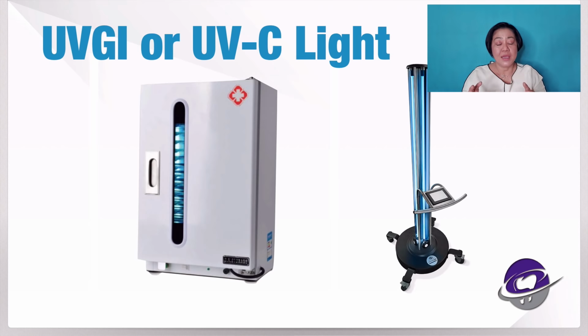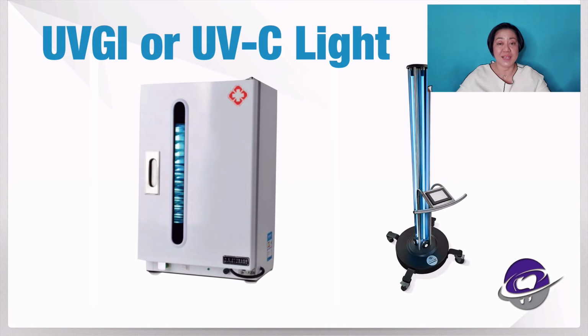However, as I've said, there is still a discussion whether it can be considered as sterilization or just simply disinfection. But for me, I feel that if you have a clinic that serves a lot of patients, then I think the best way to do is clean all the surfaces first and then run this UVGI or UVC. Now, when you buy this, make sure that you understand how big your room is, because again, just like the autoclave, the light has to have direct contact to the surface for it to really work. So the nooks and crannies will not be sterilized or disinfected. So you have to make sure that you still have a disinfectant solution to deal with these small areas that the UVC or the UVGI cannot reach.